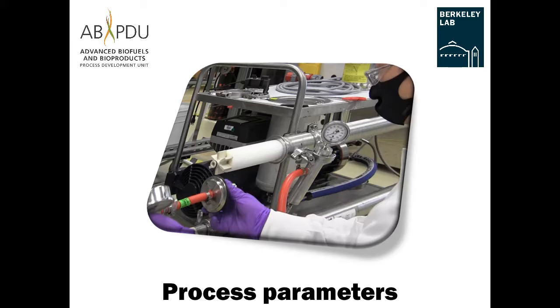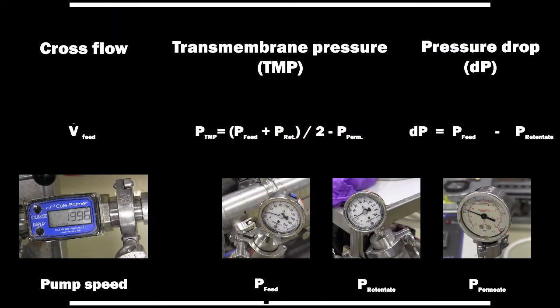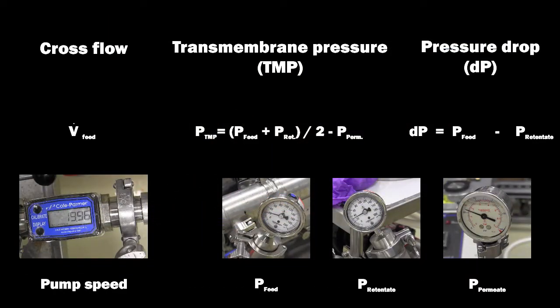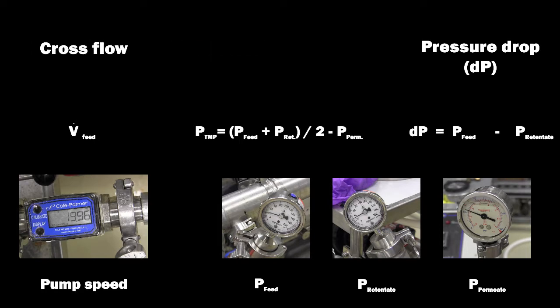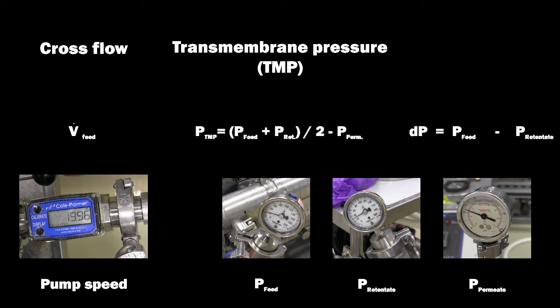Process parameters. Here we will give an overview of the key process parameters and controls involved with running the M20 system. The three key parameters are the feed crossflow rate, the transmembrane pressure or TMP, and the pressure drop or DP. It is critical that each parameter is operated within the range as specified in the membrane product documentation to ensure optimal process performance and to avoid process failure or damaging the membrane.